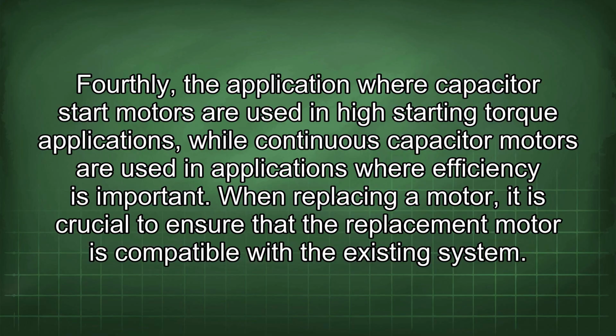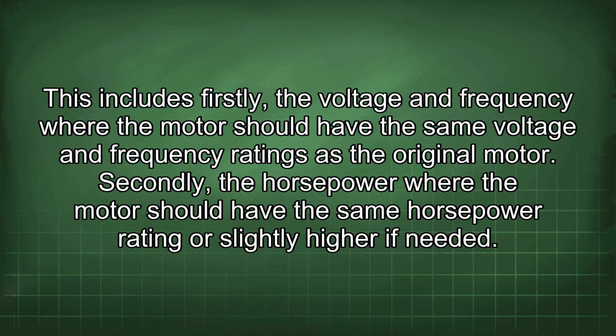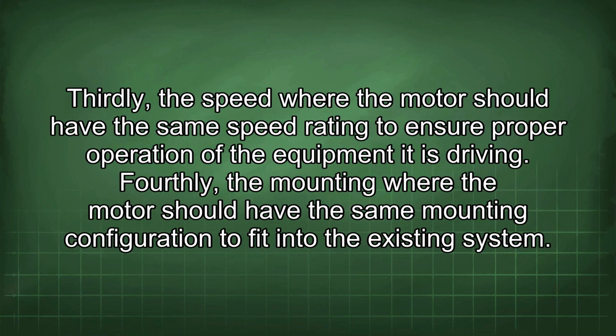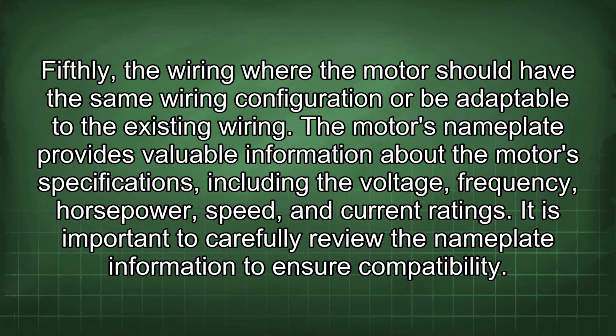When replacing a motor, it is crucial to ensure that the replacement motor is compatible with the existing system. This includes, firstly, the voltage and frequency, where the motor should have the same voltage and frequency ratings as the original motor. Secondly, the horsepower, where the motor should have the same horsepower rating or slightly higher if needed. Thirdly, the speed, where the motor should have the same speed rating to ensure proper operation of the equipment it is driving. Fourthly, the mounting, where the motor should have the same mounting configuration to fit into the existing system. Fifthly, the wiring, where the motor should have the same wiring configuration or be adaptable to the existing wiring.